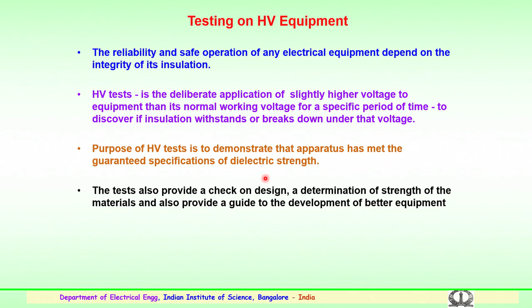Mainly we will be focusing on the insulator parts, that is ceramic, glass and porcelain. Any high voltage test which is conducted in the laboratory or in the field is expected to provide a reasonable equipment in the laboratory and employ a suitable procedure, which could be conducted in a reasonable time, which gives a reasonable assurance to the manufacturers and utilities that after the testing the apparatus is giving an expected satisfactory performance. So, with this intention the test is conducted.